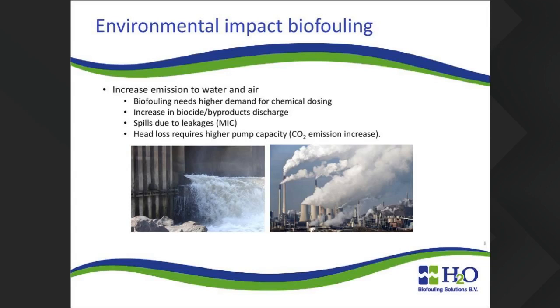When you get corrosion due to MIC bacteria, generally there's a spill of process fluid into the cooling water, which is discharged at the outlet. Head loss requires a higher pump capacity to get sufficient water into the intake basin to feed the condensers and the heat exchangers. Higher pump capacity needs and results in higher carbon dioxide emissions, which can be thousands of tons per year, only caused by head loss.